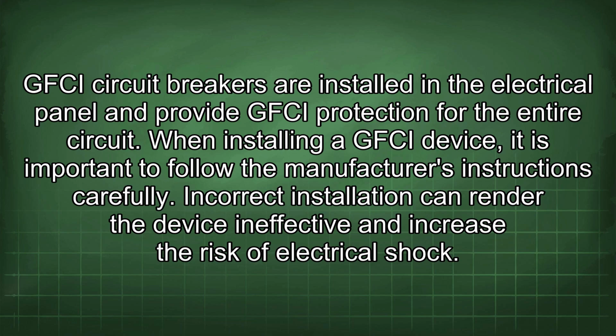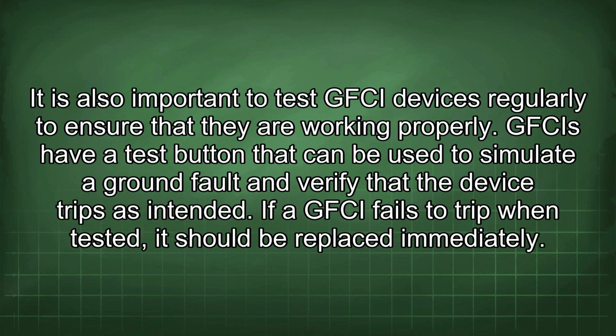When installing a GFCI device, it is important to follow the manufacturer's instructions carefully. Incorrect installation can render the device ineffective and increase the risk of electrical shock. It is also important to test GFCI devices regularly to ensure that they are working properly. GFCIs have a test button that can be used to simulate a ground fault and verify that the device trips as intended. If a GFCI fails to trip when tested, it should be replaced immediately.